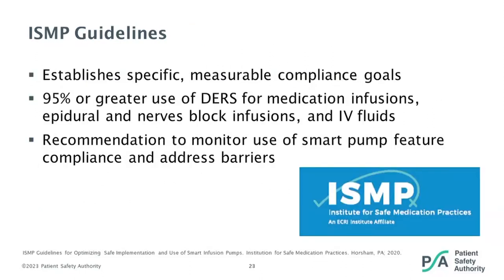Preceding these recommendations, in 2020, ISMP published guidelines for optimizing smart pump technology. These guidelines establish specific, measurable goals for compliance with smart pump safety features, including setting a 95% threshold for use of dose error reduction software for any medication or fluid infusion. Also included are recommendations for cleaning, maintaining, and adding equipment, reporting adverse events, maintaining the drug library, tracking, continuous quality improvement, clinical workflows, and interoperability.